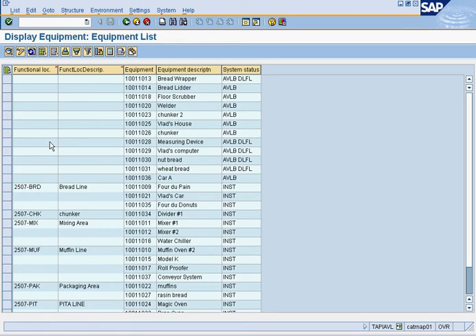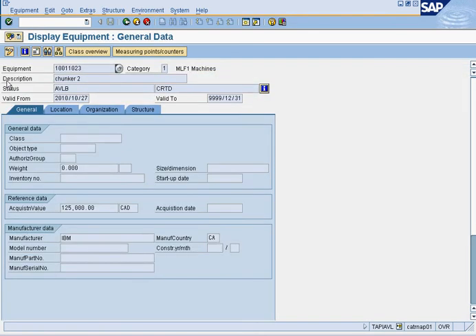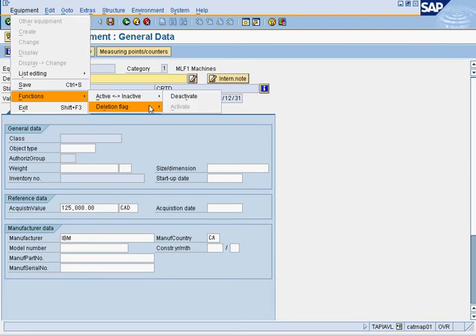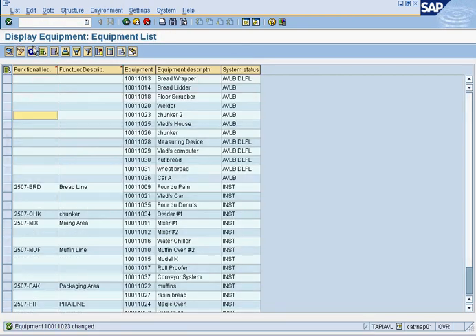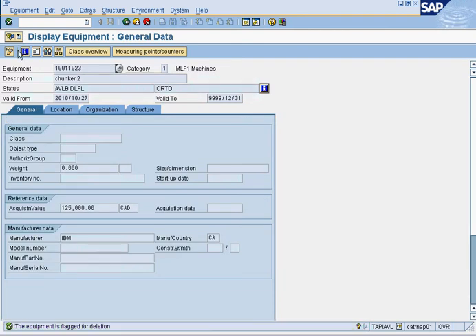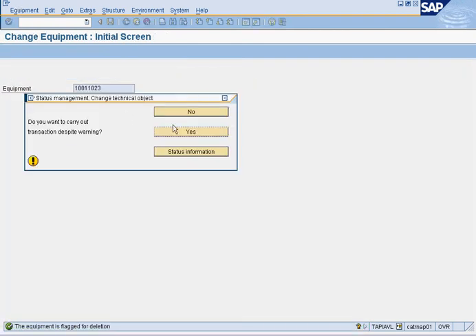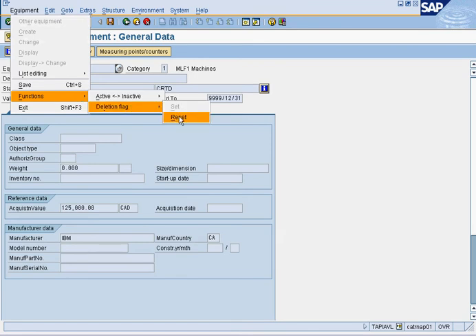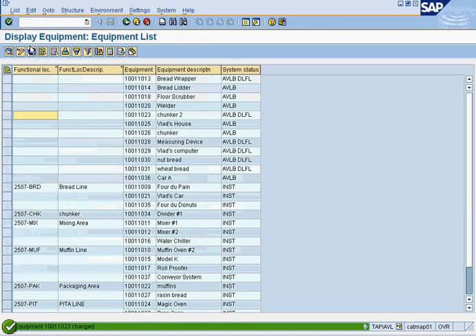We could also delete things. For example, click on an item, press change mode, go to equipment, functions, and set the deletion flag — save. Refresh, and it now has the deleted flag. You can always go in and undelete it: change mode, equipment, functions, deletion flag reset. That means it's not deleted anymore.